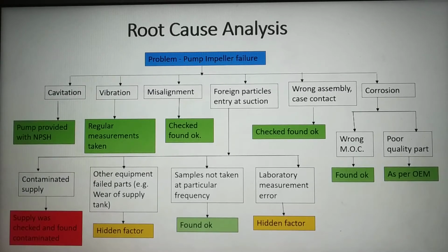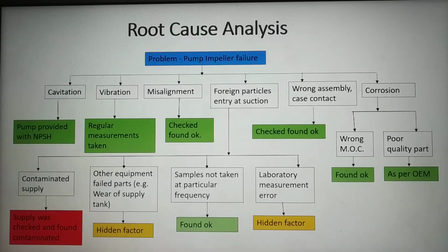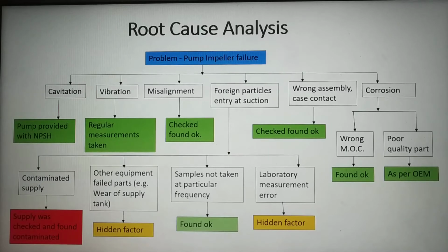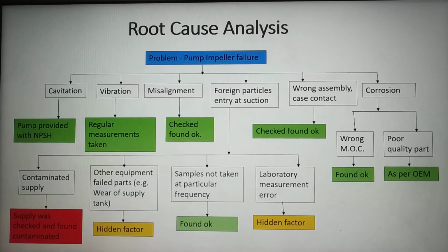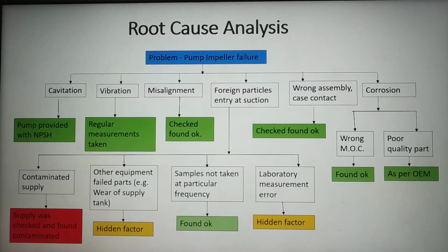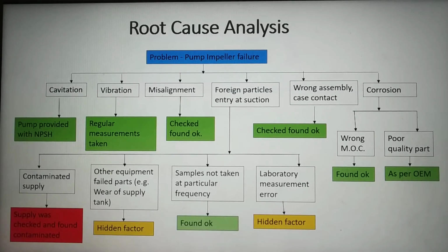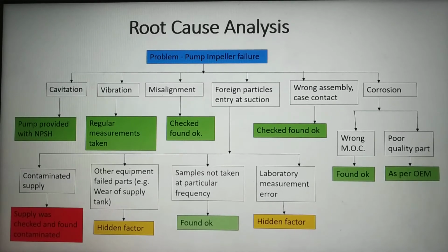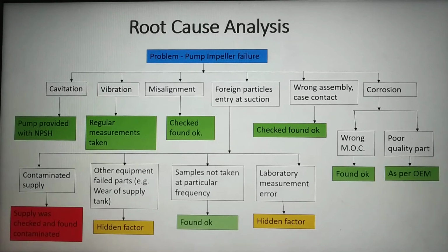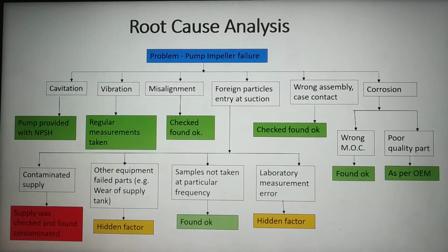And what we have to do now is check each and every reason, whether this can be the cause for the pump failure or not. So let's start with the cavitation. Can cavitation happen inside the pump? Here it is written that the pump is provided with NPSH. So the cavitation can't be there in the pump. So this is not the cause for the pump impeller failure. So let's move to the next.